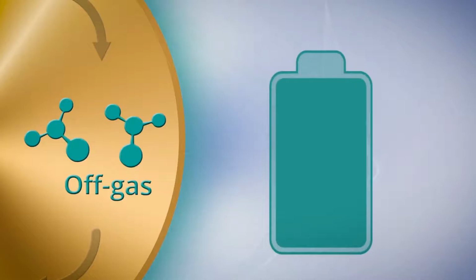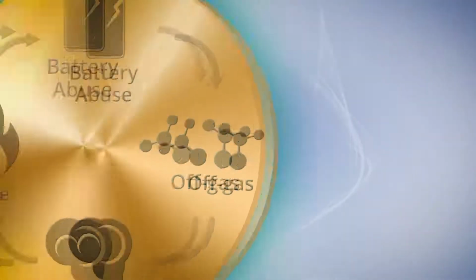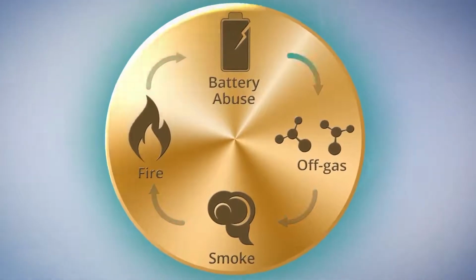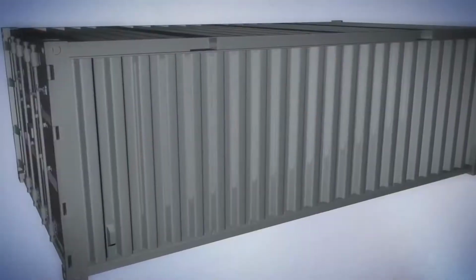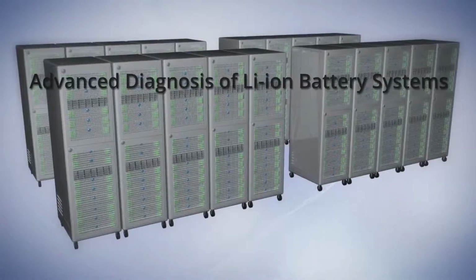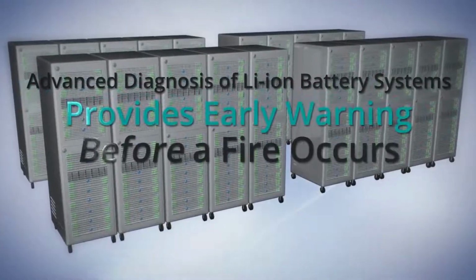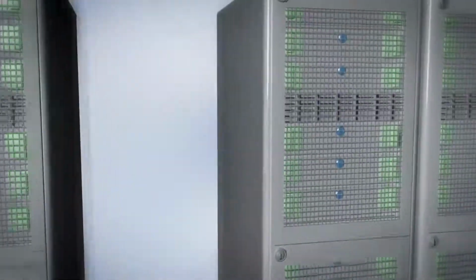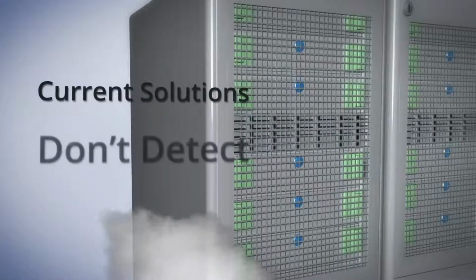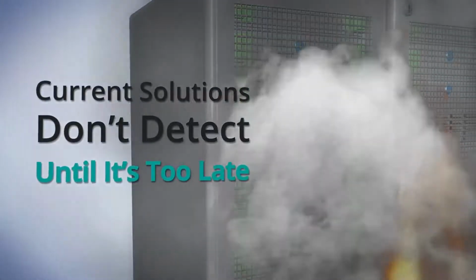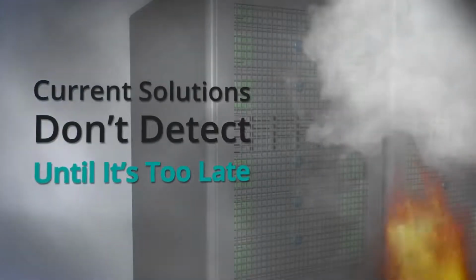Off-gas generation happens as a battery cell begins to fail. Electrolytes break down and generate gas. This gas causes an internal pressure buildup, which ultimately is released from the cell in an off-gas event. Knowing when this event occurs allows time to prevent or mitigate a battery failure. Advanced diagnosis of lithium-ion battery systems means early warnings before a fire occurs. Current solutions don't help until it's too late, often at smoke or fire detection.